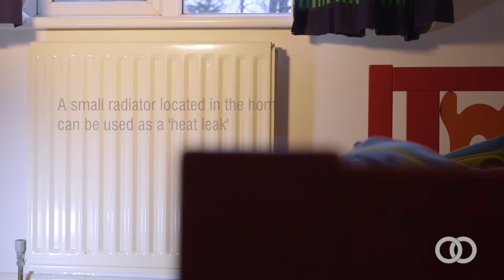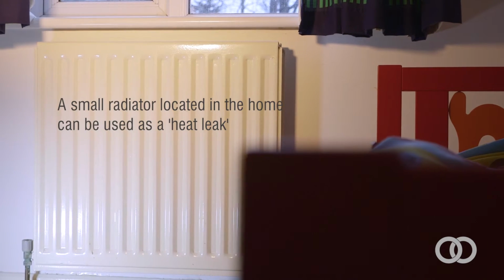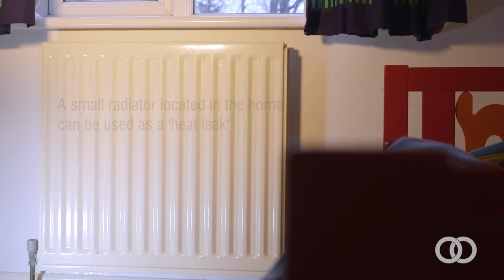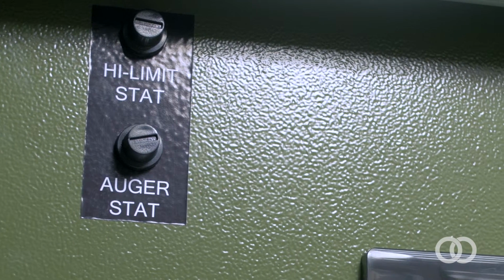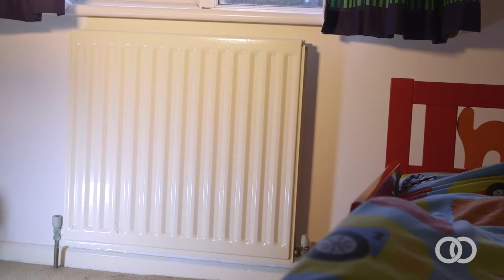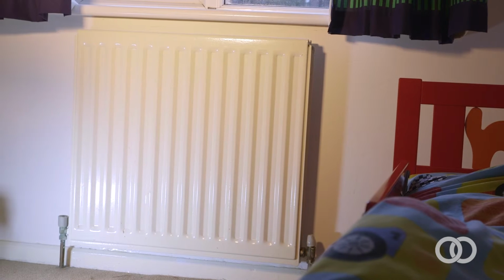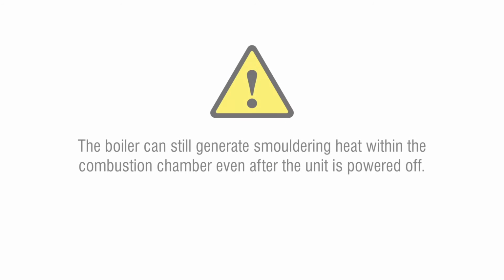It is important that there is sufficient heat leak on the system to absorb any latent heat from the boiler and to prevent nuisance tripping of the boiler overheat thermostat. This is something first-time installers of biomass boilers often overlook. The boiler can still generate smouldering heat within the combustion chamber even after the unit is powered off.